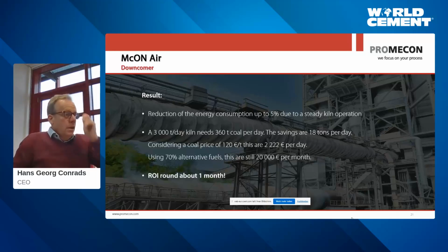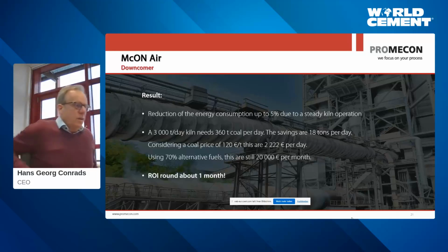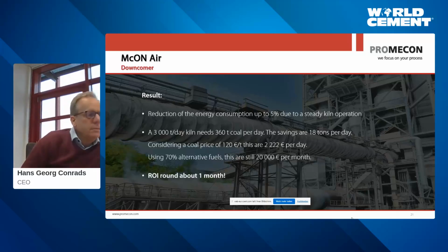So therefore, making a fan or any control loop run flatlined will always save you energy on the fan, always, automatically. So on a 3,000 ton per day kiln, yeah, I mean the savings are gigantic. We're talking tens of thousands per month. Again, if you put this in, you tie it into your control loop, you can get this investment back in very short time.